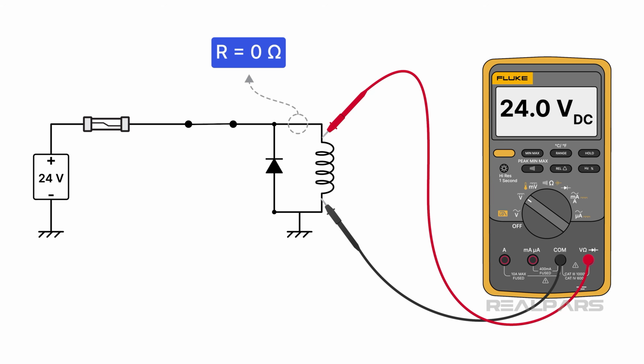Good wires and terminals have virtually 0 resistance, so there is no voltage drop across them. But if either has an increase in resistance, you no longer have a 0-volt drop across them. So, if you have a solenoid that chatters, you may find a lower than normal voltage across it due to a voltage drop across a corroded terminal.